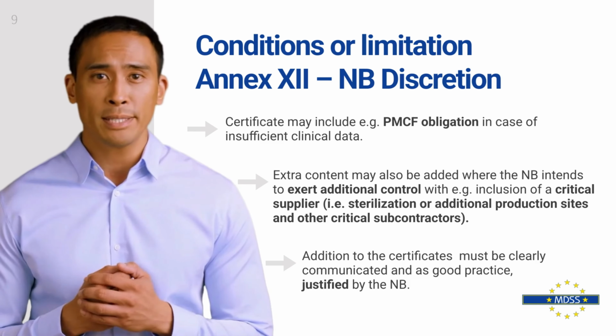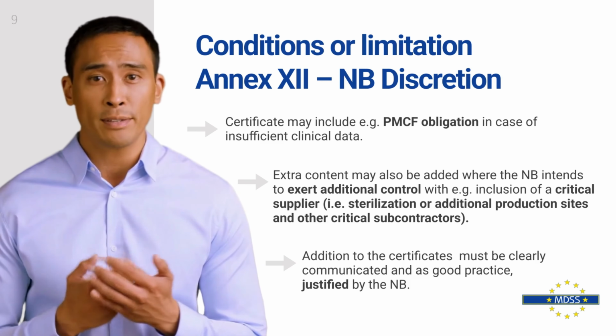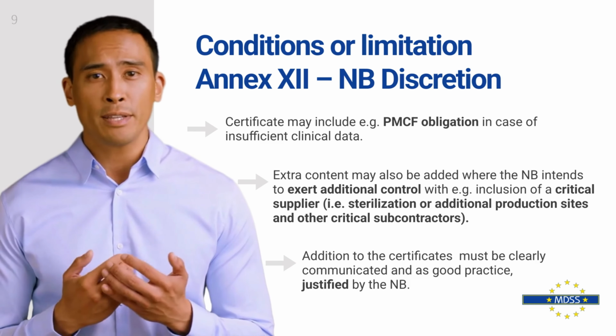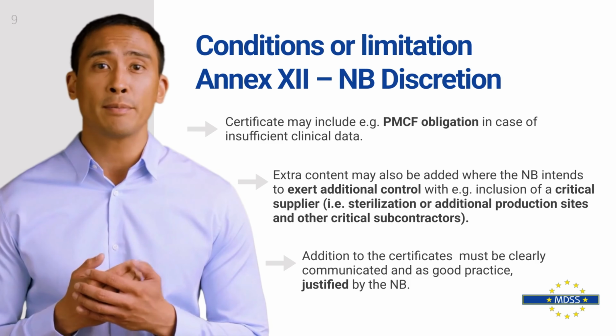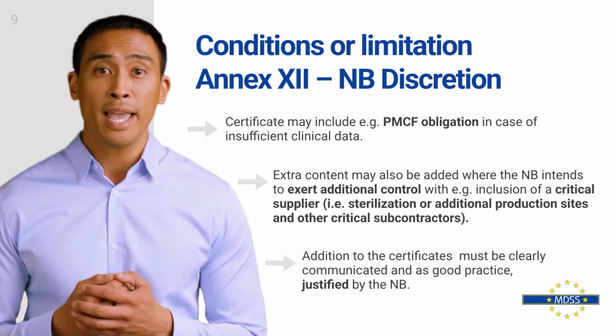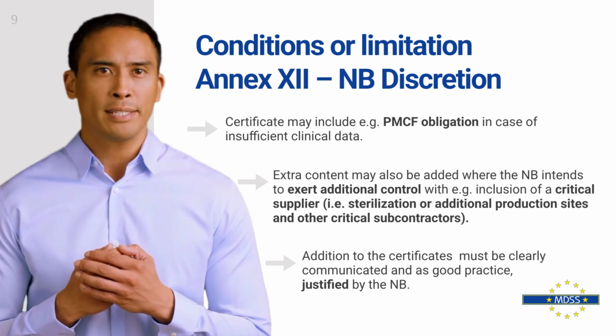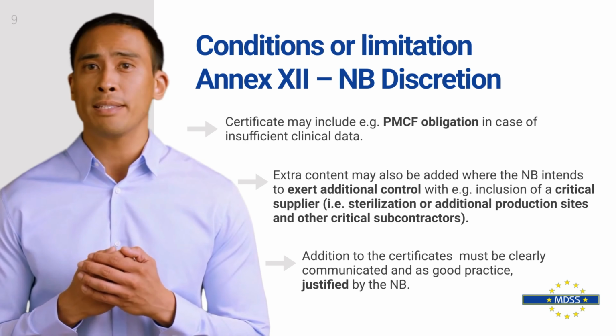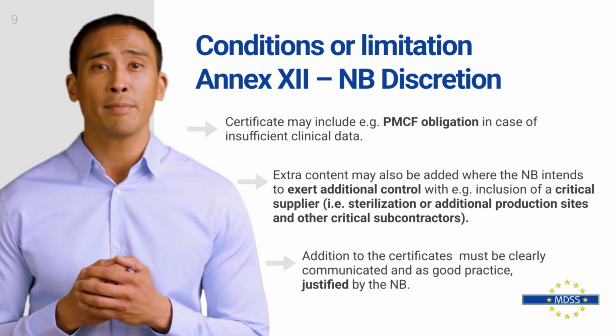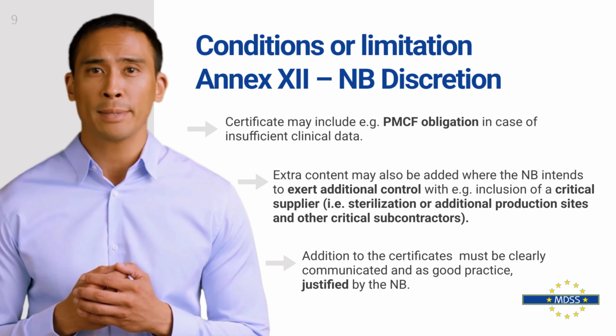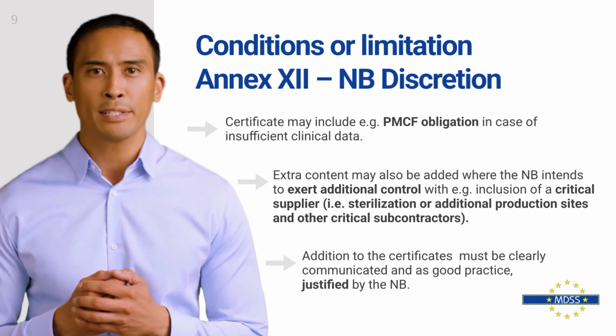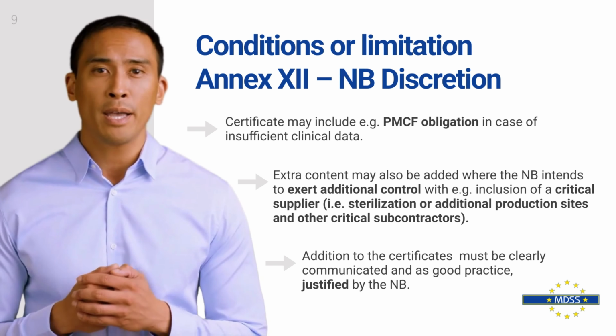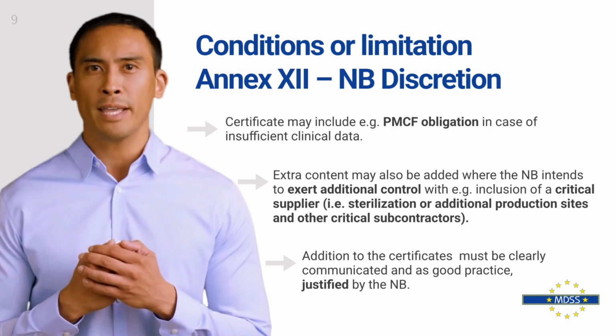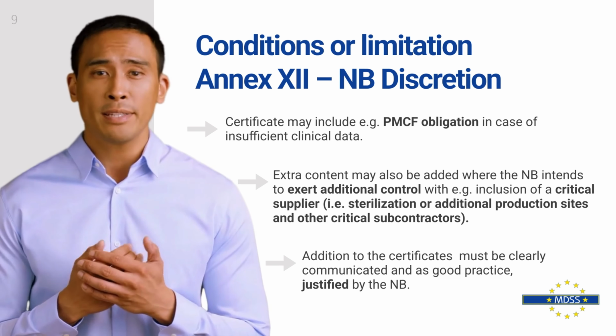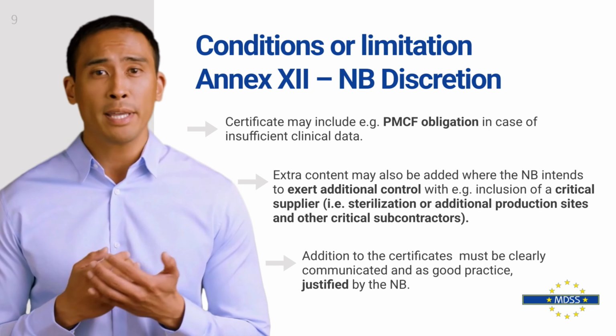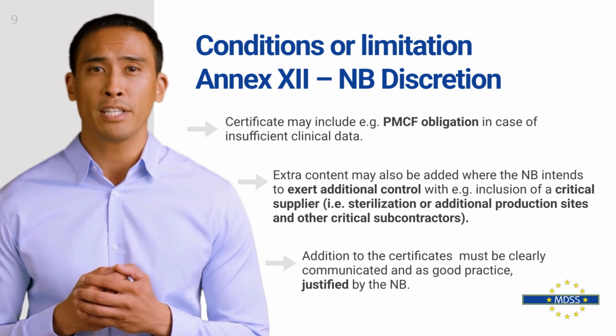Suppliers may also be listed. If a specific supplier is critical to the manufacturing or verification process, their identification might appear on the certificate. Any proposed change to such a supplier is a substantial change, as it may affect the certified assessment process and must be evaluated by the notified body. These examples underscore the importance of tracking what is listed on the certificate. Every element, whether it's a condition, a device group, or a critical supplier, can become the basis for determining whether a change is substantial.